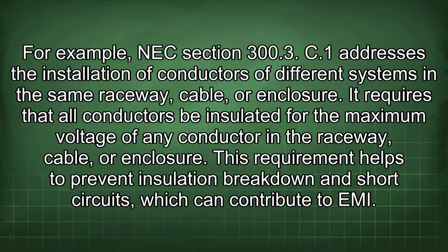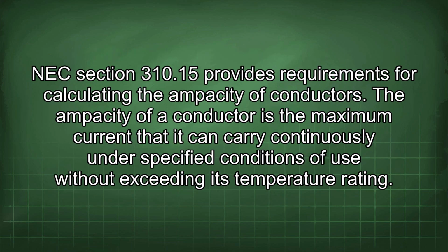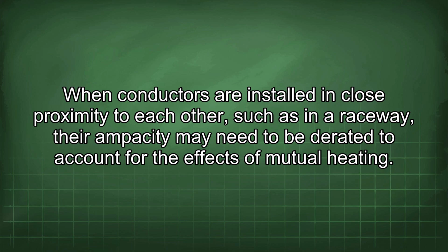This requirement helps to prevent insulation breakdown and short circuits, which can contribute to EMI. NEC Section 310.15 provides requirements for calculating the ampacity of conductors. The ampacity of a conductor is the maximum current that it can carry continuously under specified conditions of use without exceeding its temperature rating. When conductors are installed in close proximity to each other, such as in a raceway, their ampacity may need to be derated to account for the effects of mutual heating.